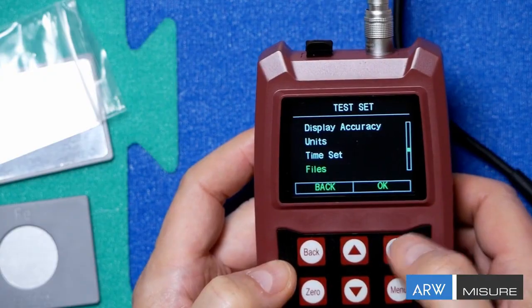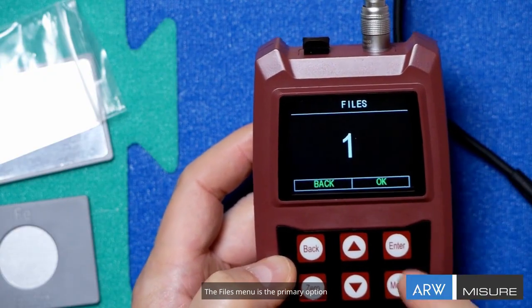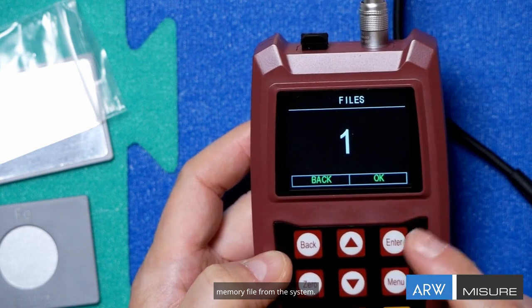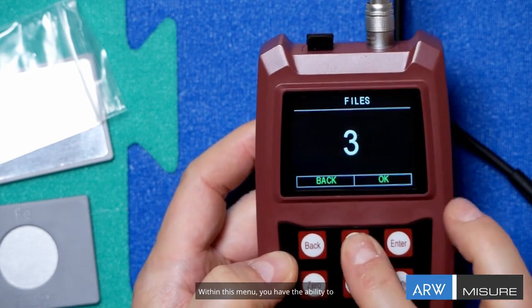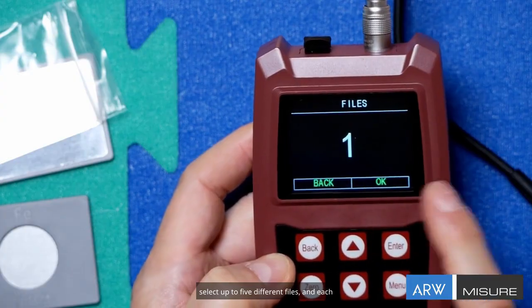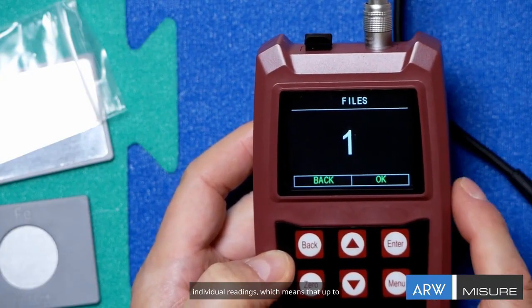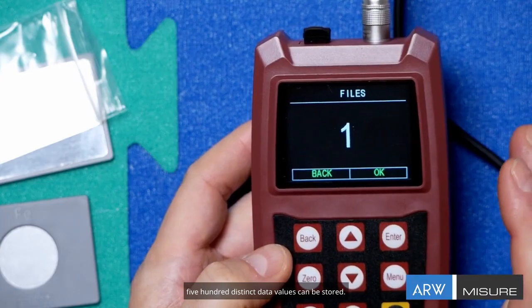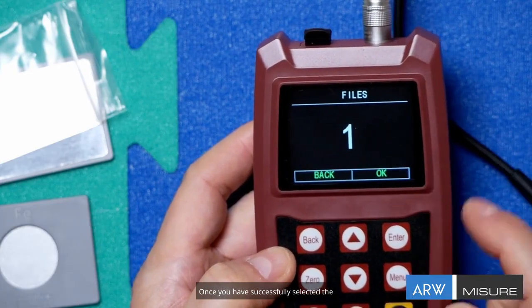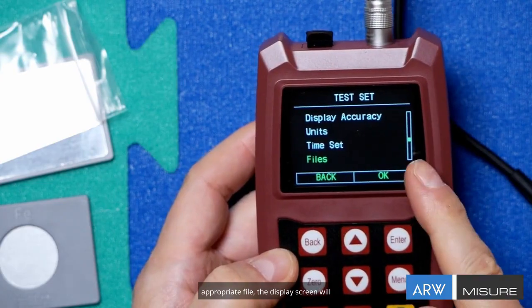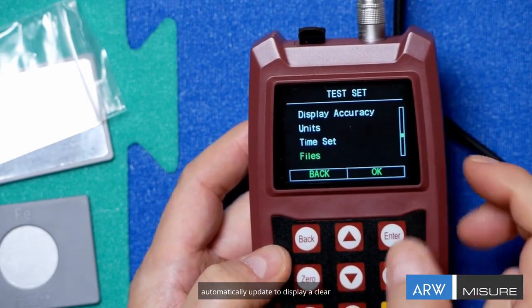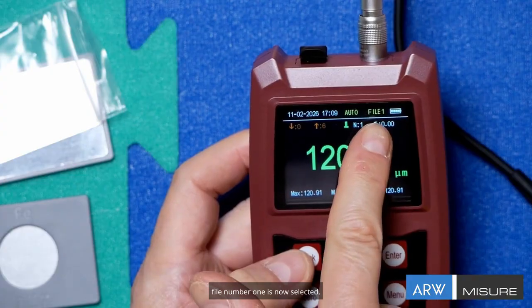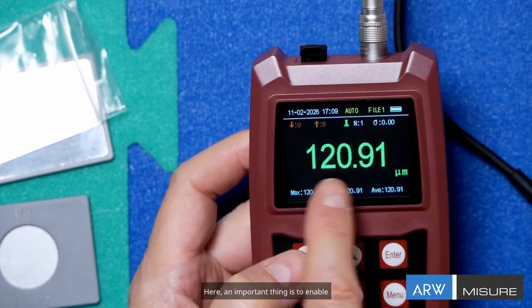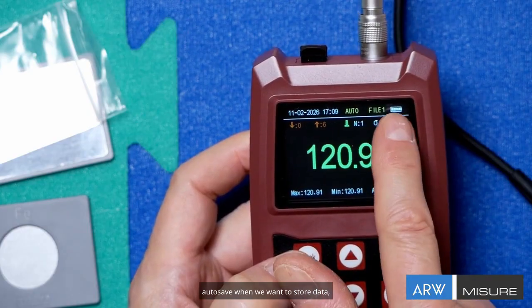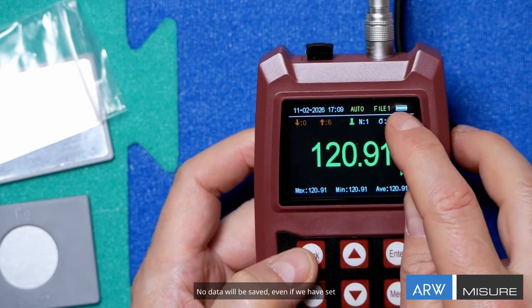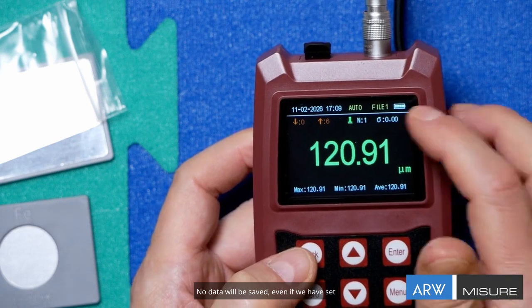Next, we find Files. The Files menu is the primary option available for you to select your desired memory file from the system. Within this menu, you have the ability to select up to 5 different files, and each of these files can contain 100 individual readings, which means that up to 500 distinct data values can be stored. Once you have successfully selected the appropriate file, the display screen will automatically update to display a clear message at the top of the screen stating that file number 1 is now selected. Here, an important thing is to enable autosave when we want to store data. Otherwise, it won't save anything. No data will be saved, even if we have set the file.